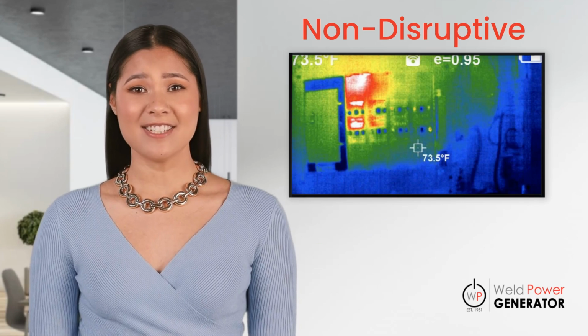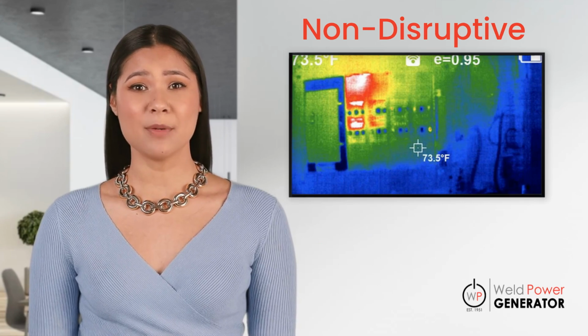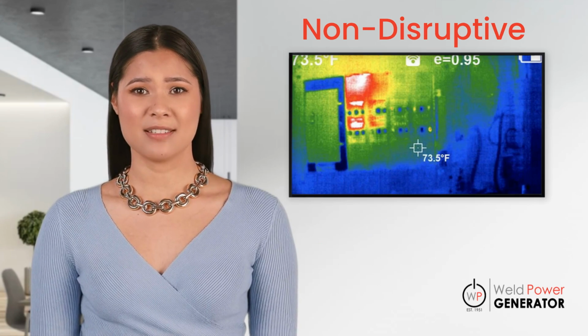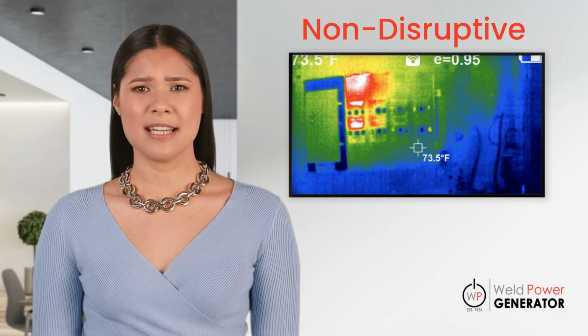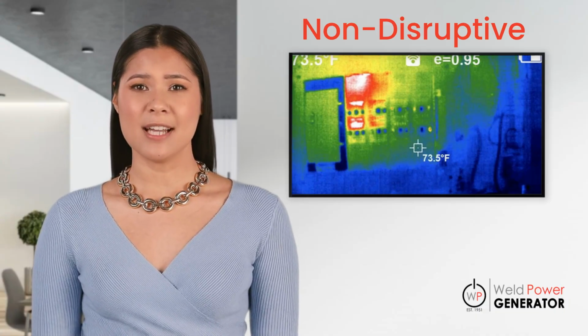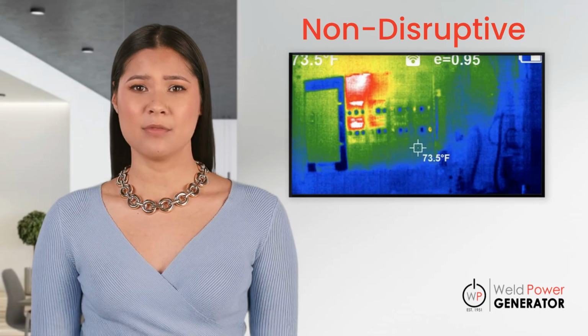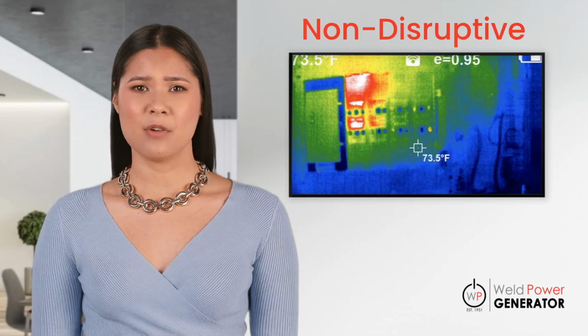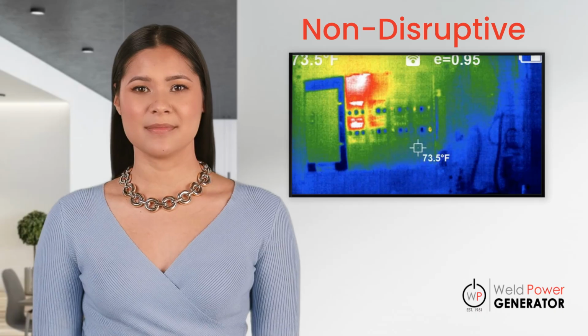One of the biggest advantages of thermal imaging is that it can be performed without interrupting operations. Technicians can conduct thermal scans while the ATS is under load, capturing a real-time picture of how the system performs under stress. It's also safer for personnel as inspections are performed at a distance without opening energized panels unnecessarily.